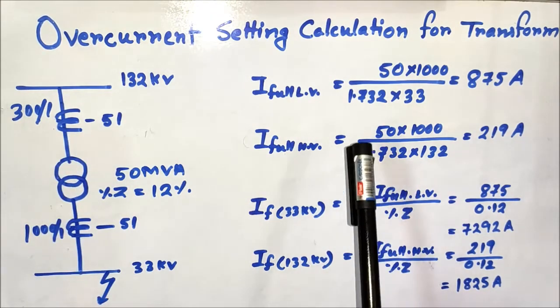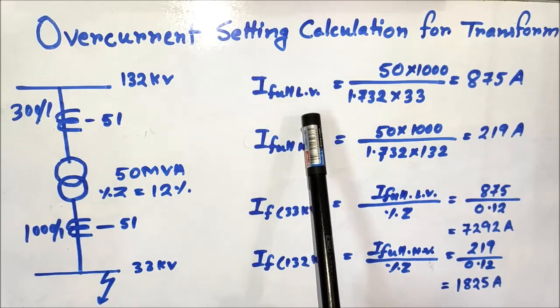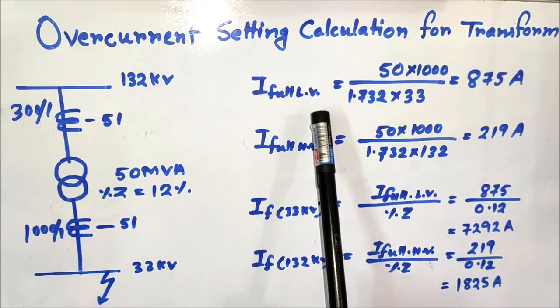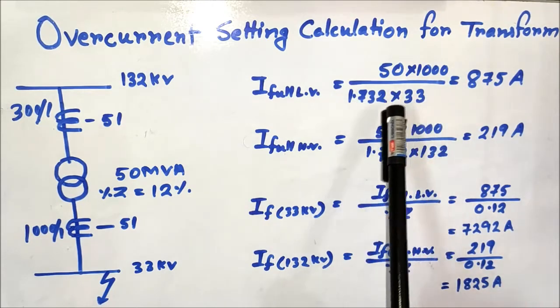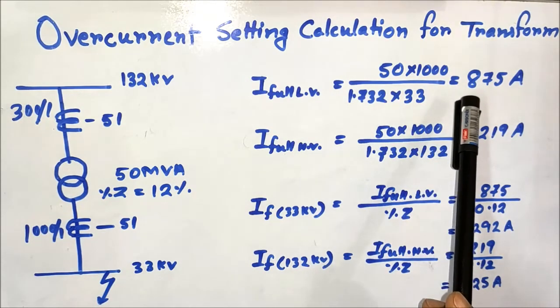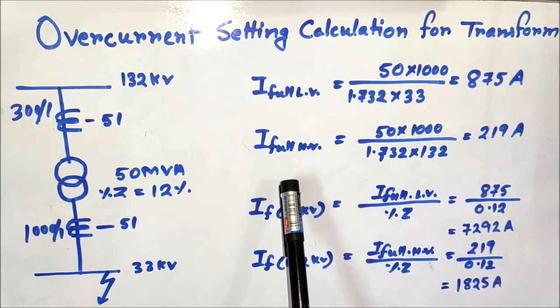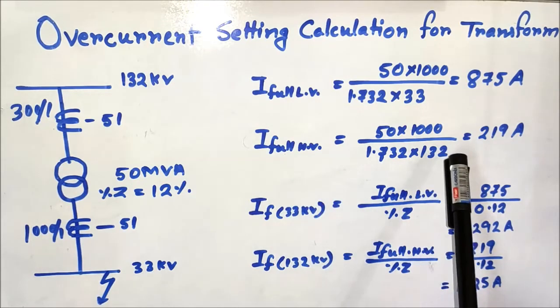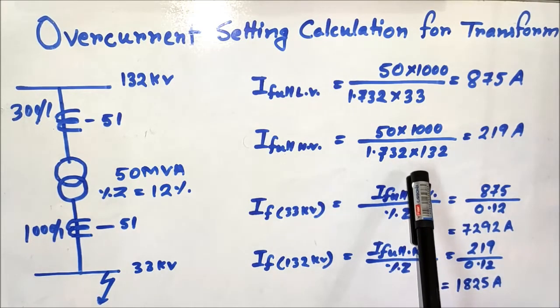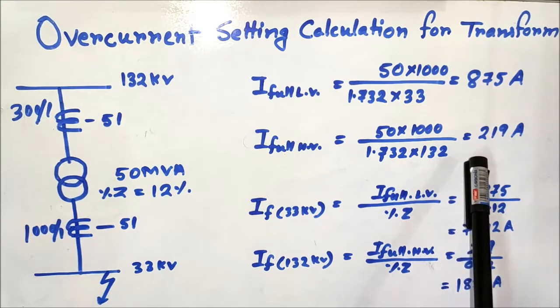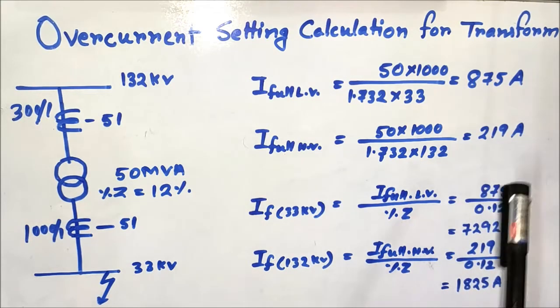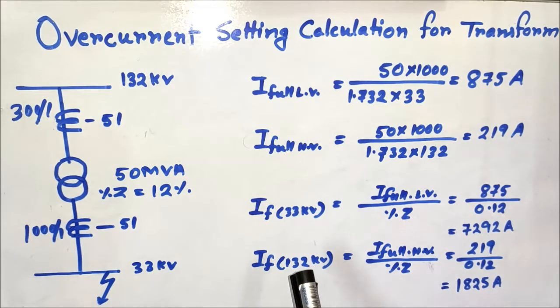The full load current for the LV side (33kV side) is given by 50×1000 divided by √3×33, which comes to approximately 875 amperes. The full load current for the HV side is 50×1000 divided by √3×132kV, which comes to approximately 219 amperes.